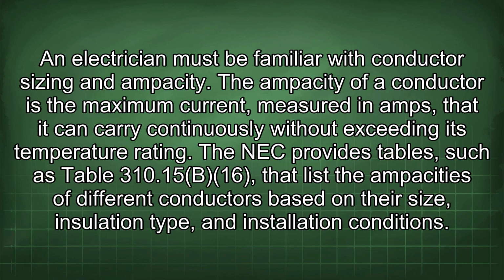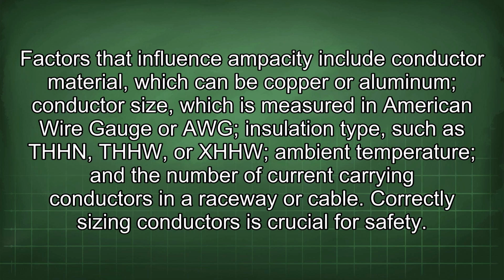An electrician must be familiar with conductor sizing and ampacity. The ampacity of a conductor is the maximum current, measured in amps, that it can carry continuously without exceeding its temperature rating. The NEC provides tables, such as Table 310.15(B)(16), that list the ampacities of different conductors based on their size, insulation type, and installation conditions. Factors that influence ampacity include conductor material, which can be copper or aluminum, conductor size, which is measured in American Wire Gauge or AWG, insulation type such as THHN, THWN, or XHHW, ambient temperature, and the number of current carrying conductors in a raceway or cable.